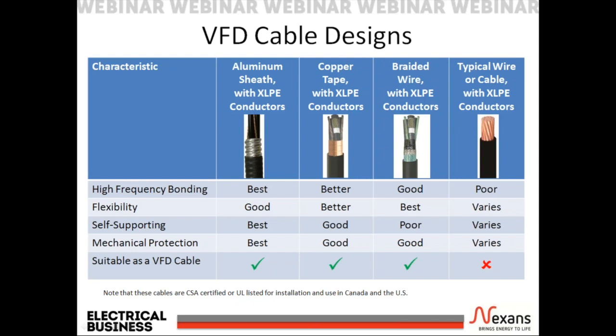So when it comes to suitability for installation in a VFD system, any one of the first three VFD cables should be selected, based largely on the installation environment. Typical wire and cable not identified as a VFD cable, such as RW90 in conduit or Teck 90 cables, should not be used for VFD applications.